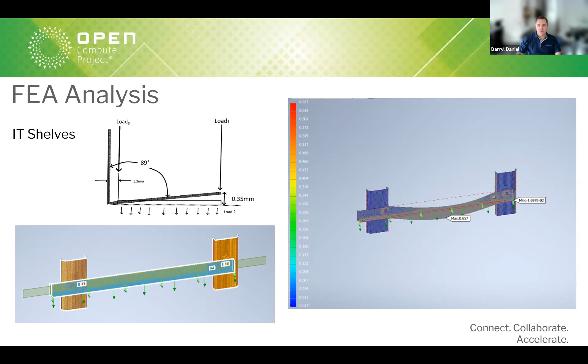We did some FEA point load analysis, with two individual point loads. The first was at the 89-degree position of the shelf, where the equipment would initially contact it. As that deflects down, the point of load would shift to the far left-hand side of the shelf, where it would become stronger. The FEA showed that at the higher levels of equipment load, we got a pass, which was good. So for the OU shelf and the power shelves, we've proven with FEA analysis that we won't get an issue with the highest levels of load.